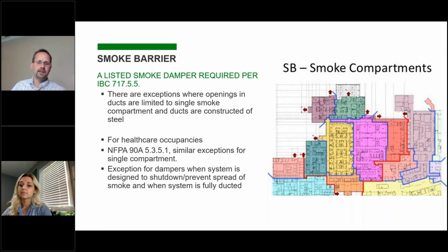That's why it's important early on in a design project to understand where these smoke barriers are and try to think that through as you're laying out ductwork, laying out systems, to minimize the number of penetrations to make it easier for the owner in the long term of the project. Another exception was new in the 2015 IMC. It's saying smoke dampers aren't required in I2 Condition 2 systems that are fully ducted, fully sprinkled with quick response sprinkler heads. So I2 Condition 2, that's mostly like behavioral health. Condition 2 refers to places where people have free movement, yet egress out is locked. So that would be a behavioral health type situation. So you can look at that if you're under the 2015 or greater, and in one of those projects, is something to look into to see if that additional exception could be taken advantage of.